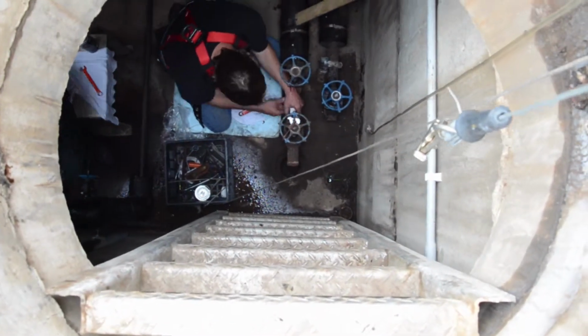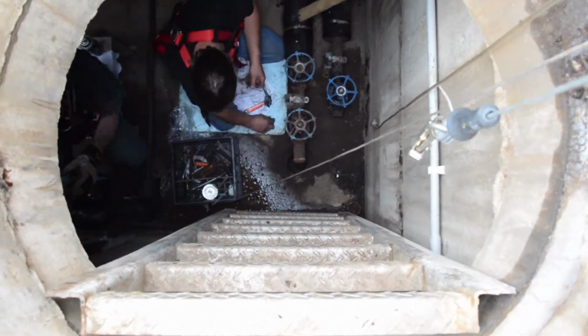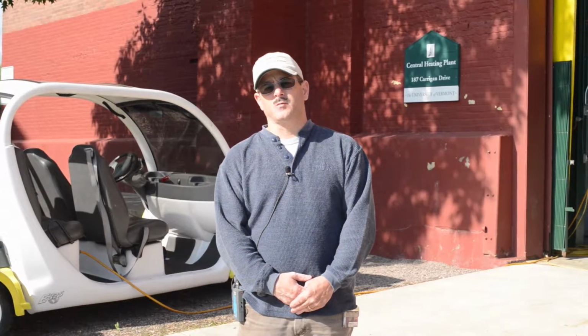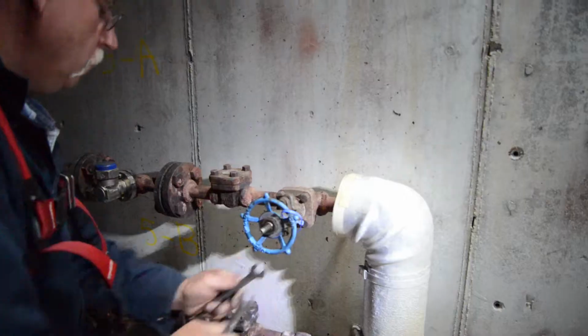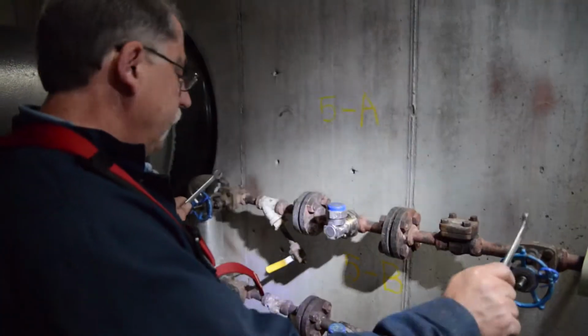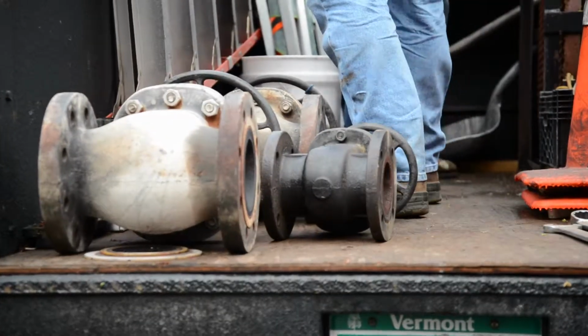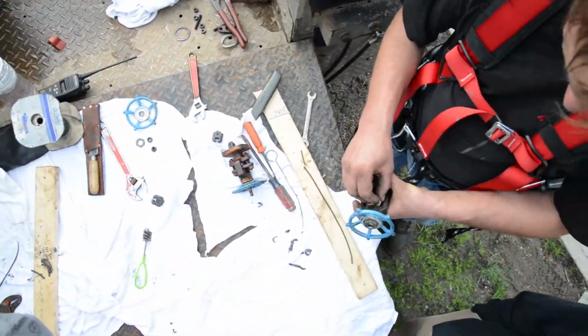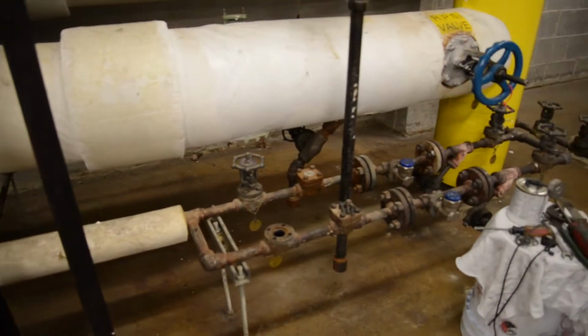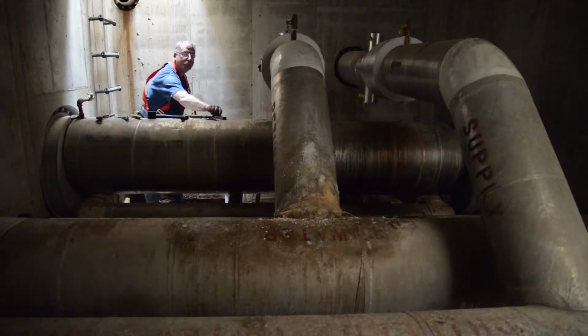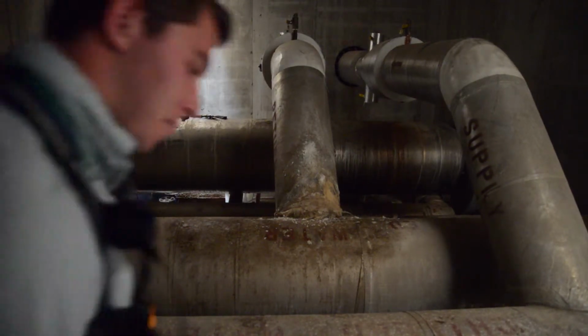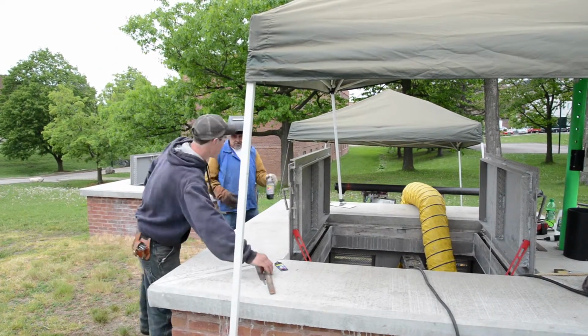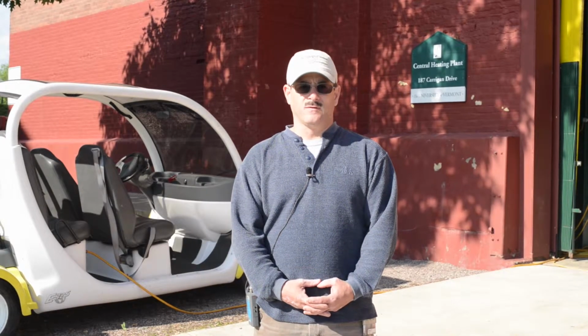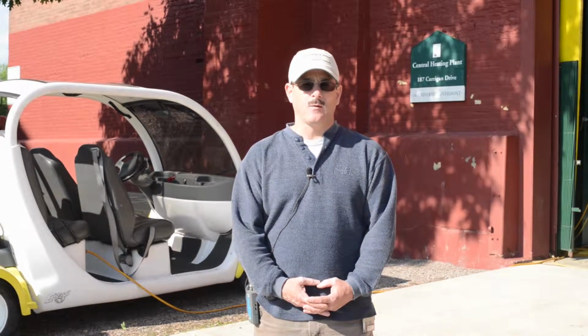At this point in time, we have about 40 vaults we pull maintenance on. Part of the maintenance is we go in and make sure all the valves are operating, all the trap stations are operating. If they're not, we replace them. We pack the valves. We also have about 24 steam stations in the buildings on campus that we do maintenance on also. And we have about 6 miles of high pressure steam piping underground, about 1,000 steam traps that we're doing maintenance on during the shutdown, and thousands of valves that we're doing maintenance on during that week.